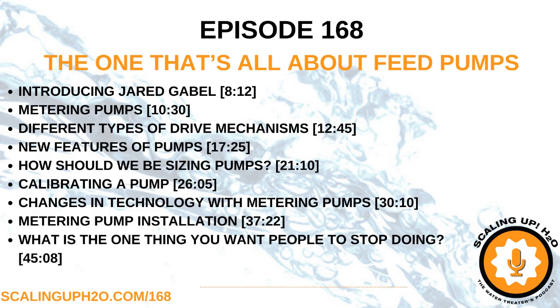So steady state accuracy, basically, is where the accuracy sits relative to my set point. When you're looking at the accuracies of different manufacturers, key in on what they mean by their accuracy. Is it plus or minus 1% of the maximum allowable flow rate? Or are you talking about the accuracy of the set point that you select? Because those are going to differ quite a bit. So that's one thing to really pay attention to.